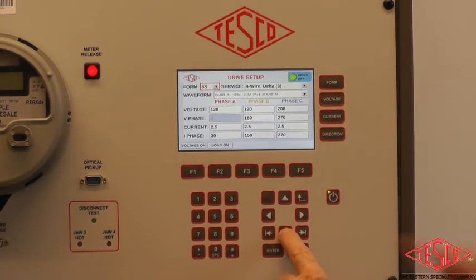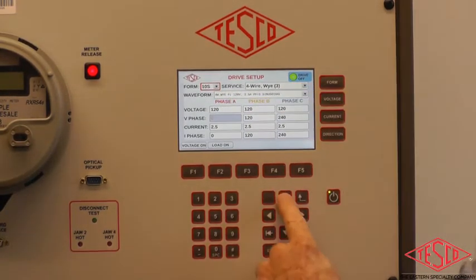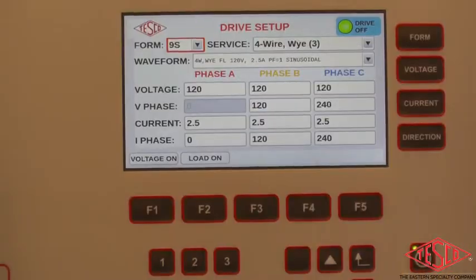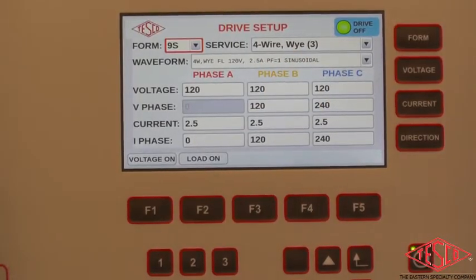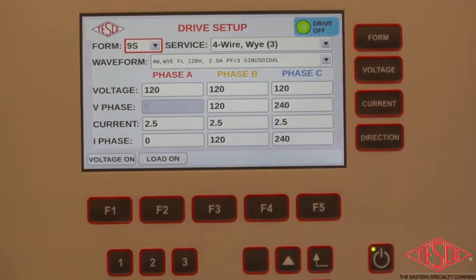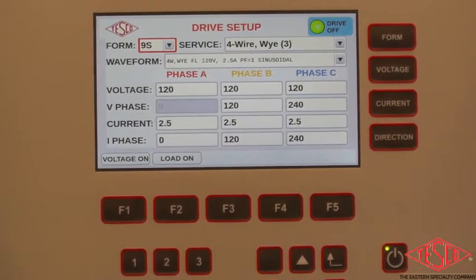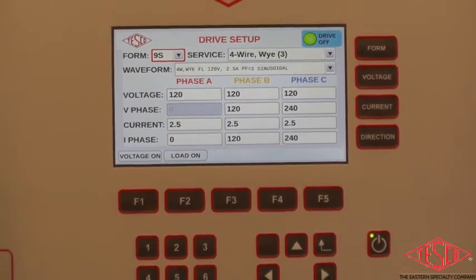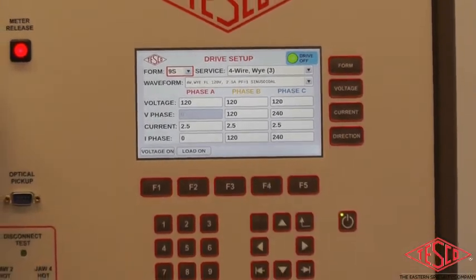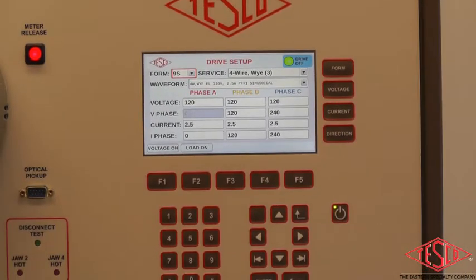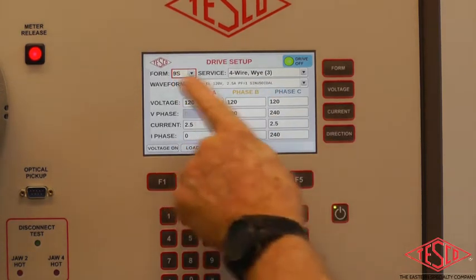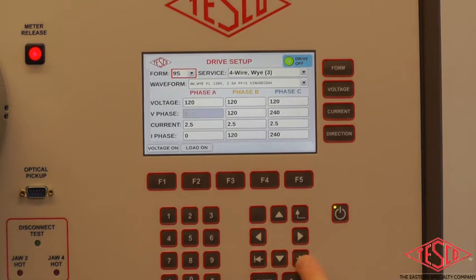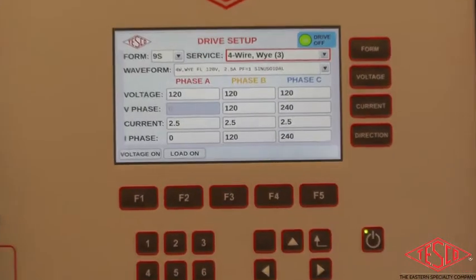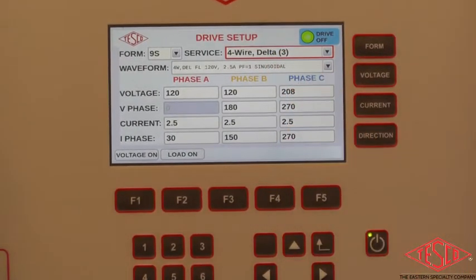And you'll see that all these forms come up automatically. When I get to 9, it's automatically form 9. It comes to a Y. You can change the services. There are various services allowed. I won't get into it in too much depth here, but there are various services allowed for a 5S meter, for a 2S meter, for a 9S meter. The default is a 4-wire Y. But if you want to change the field, the way to do it is to press these side arrow keys here. You go to the 4-wire Y, and press down, and it becomes a 4-wire delta.